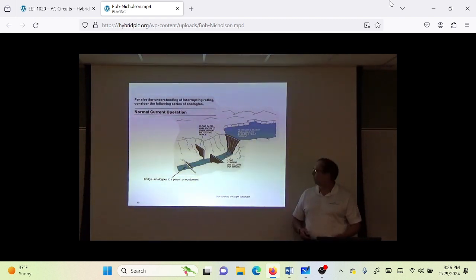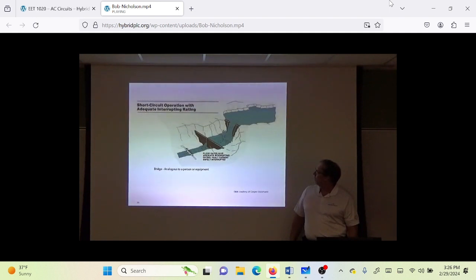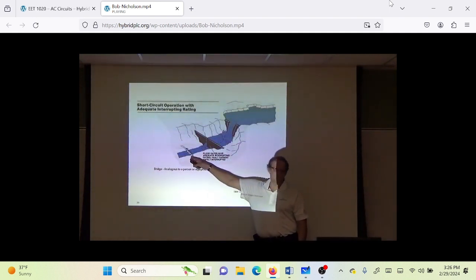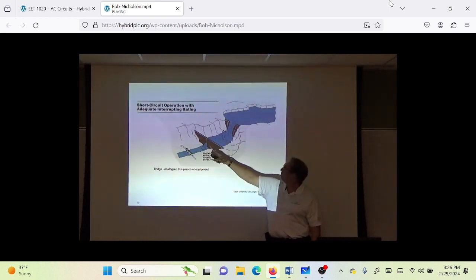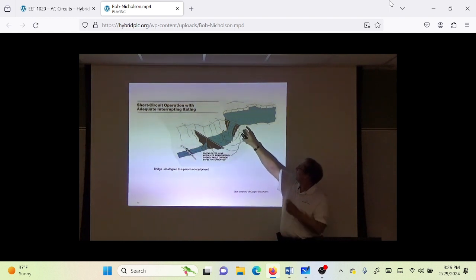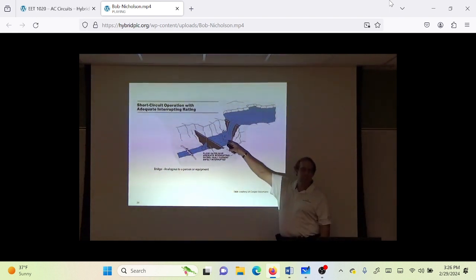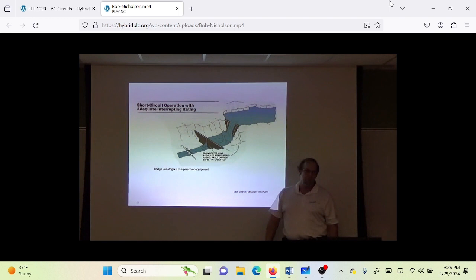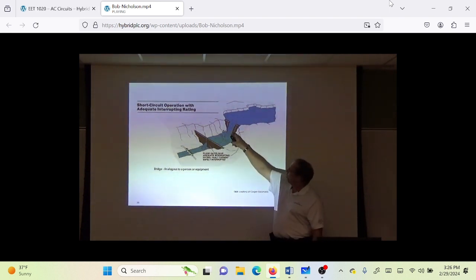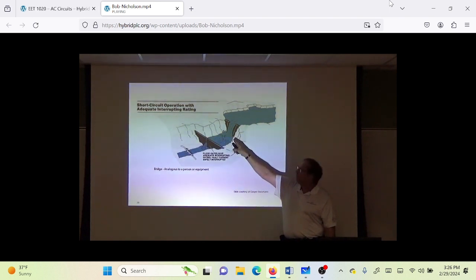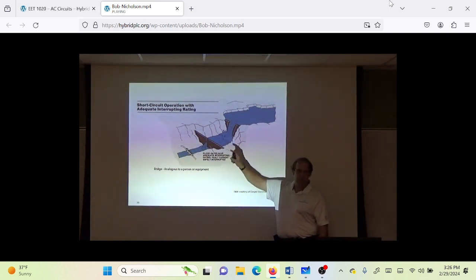Now, here's the spooky part. There's the reservoir, which is the transformer. There's the sub-panel. The instant that this fault occurs here, that's the speed of electricity. Anybody know that speed? Really fast. Speed of light. Put that on the test. This 50,000 amps automatically comes in the building because it thinks that you need more electricity, more load. So it'll go right past this service and will not trip it. It'll run down this wire, 50,000 amps.